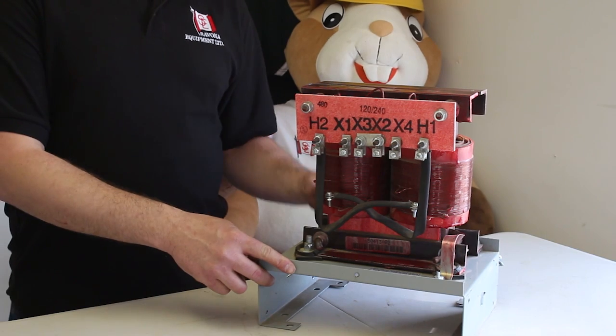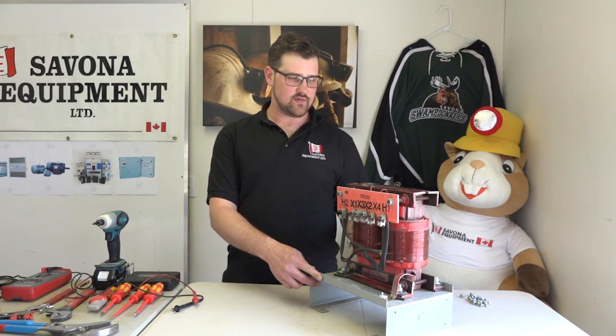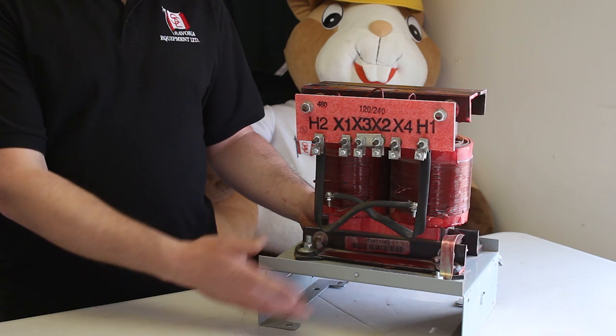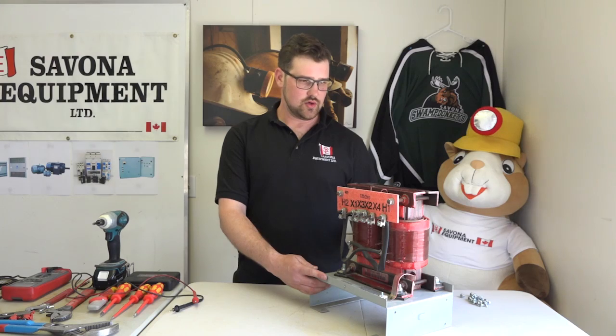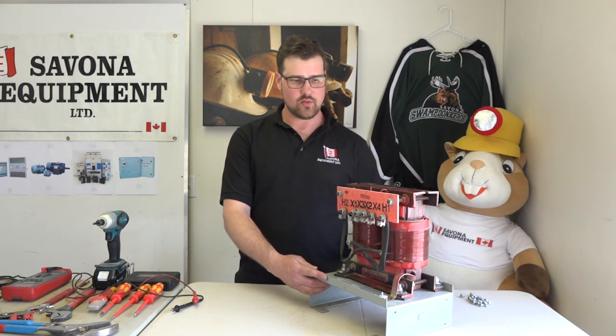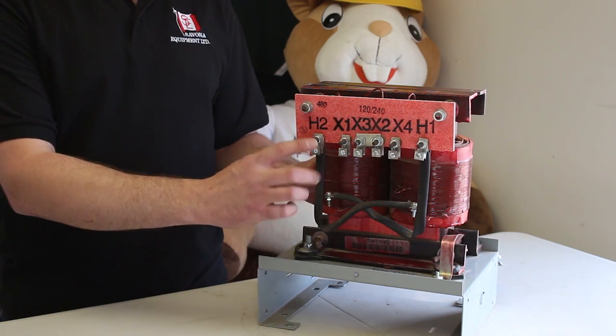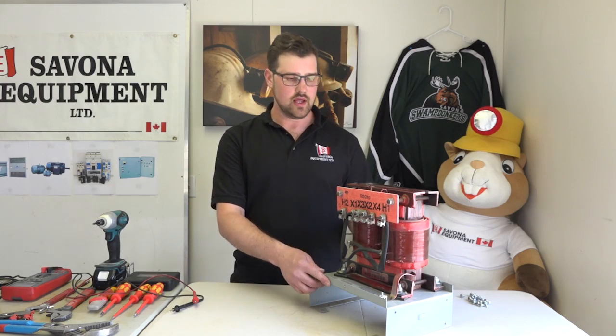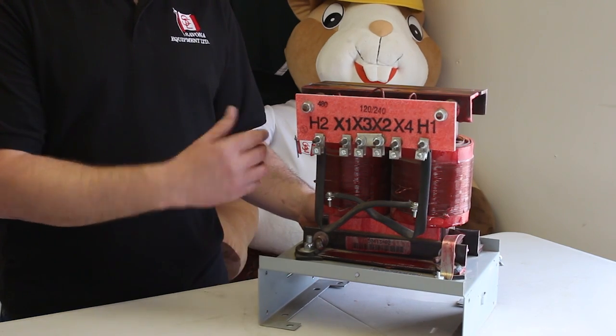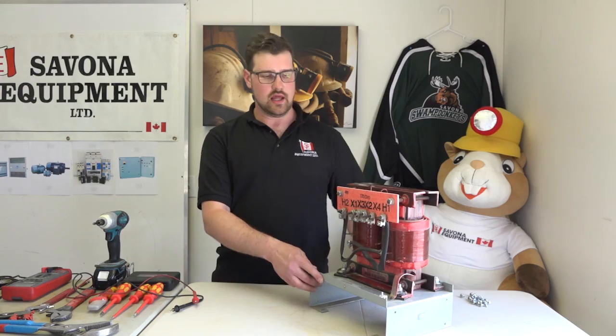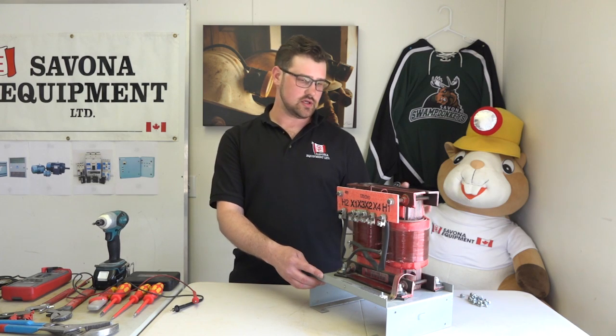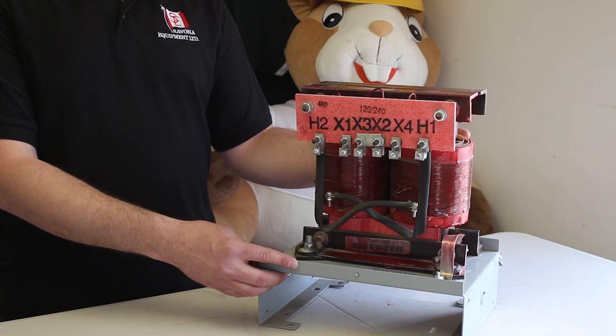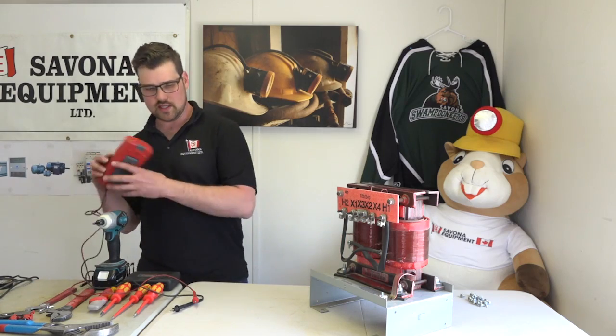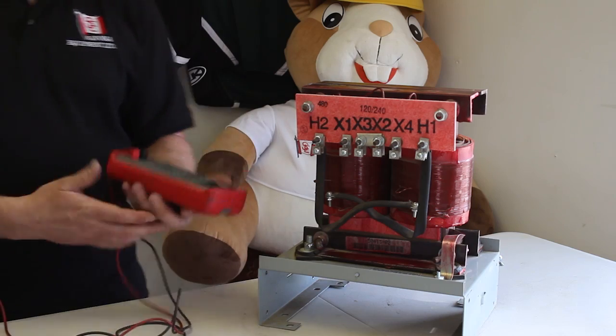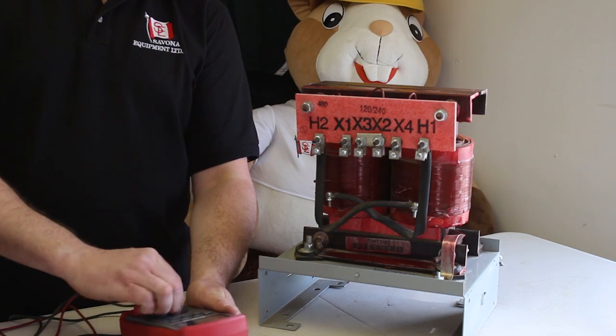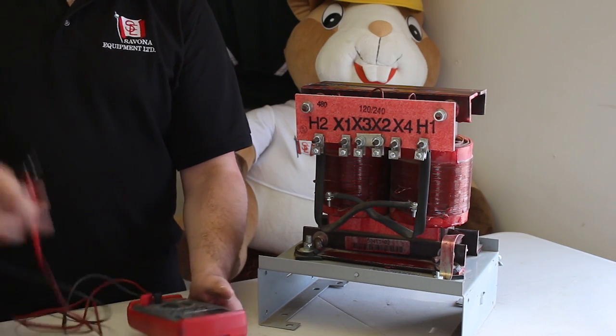Okay, so next we're gonna test the transformer and make sure that everything's good and it's ready to go into service. So I'm gonna do a quick continuity test on the windings, and then the high voltage winding to ground, the low voltage winding to ground. And the continuity test is just for checking for opens in your windings. And then we'll do a megger test after, which tests the insulation of the windings. And the continuity test is just simply done with your multimeter. You just turn it to the ohm reader.